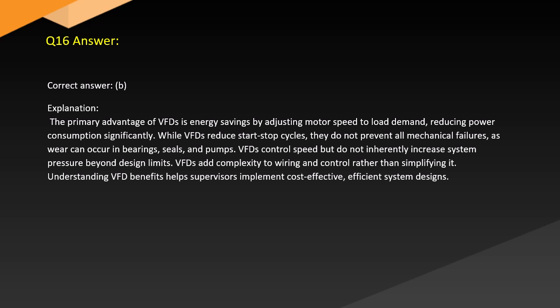Answer. Correct answer: B. Explanation. The primary advantage of VFDs is energy savings by adjusting motor speed to load demand, reducing power consumption significantly. While VFDs reduce start-stop cycles, they do not prevent all mechanical failures, as wear can occur in bearings, seals, and pumps. VFDs control speed but do not inherently increase system pressure beyond design limits. VFDs add complexity to wiring and control rather than simplifying it. Understanding VFD benefits helps supervisors implement cost-effective, efficient system designs.